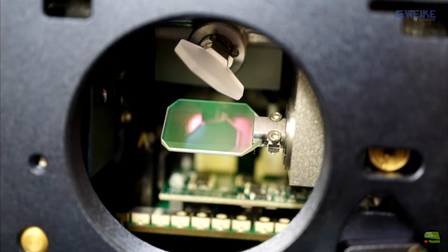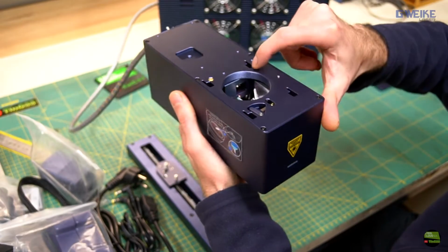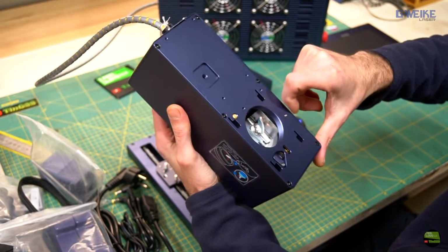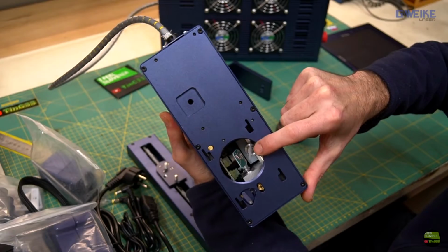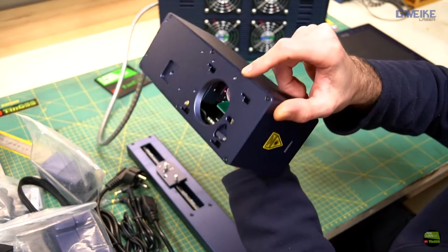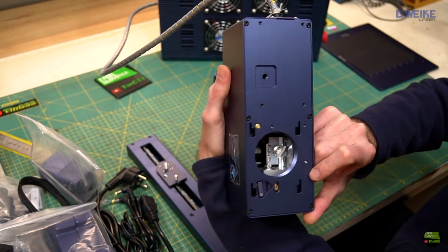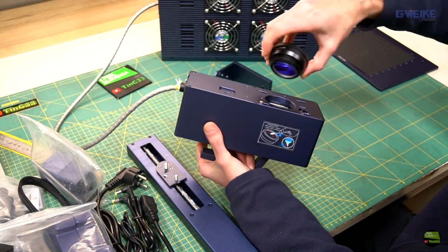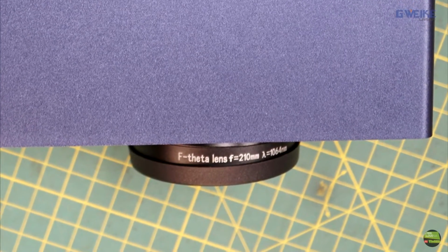If we remove the lens we can see a lot of electronics and the big galvo system inside. Now that unit is just lightweight, it's only small for 150 mm working area. I noticed that the lens is same as on manual version with focal length 210 mm, even if the electronic version has 261 mm focal point.